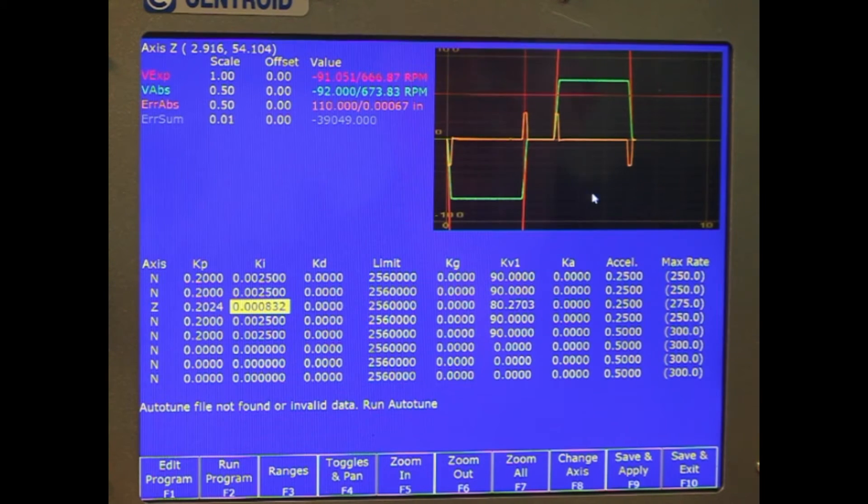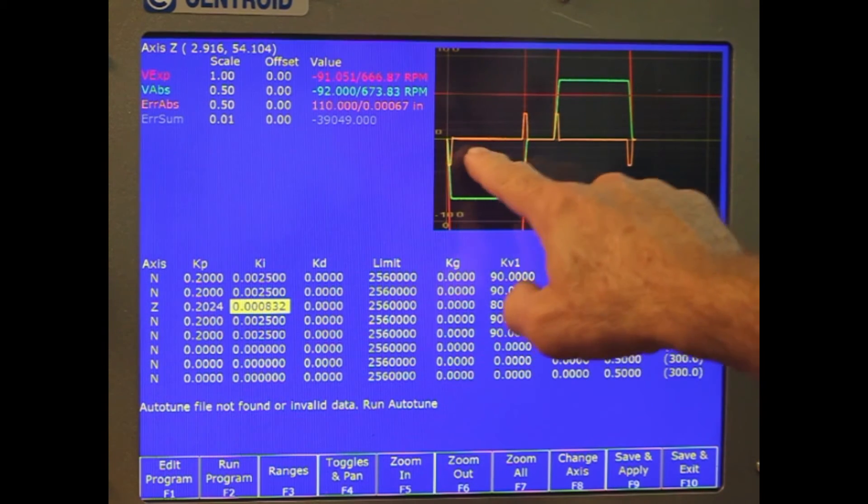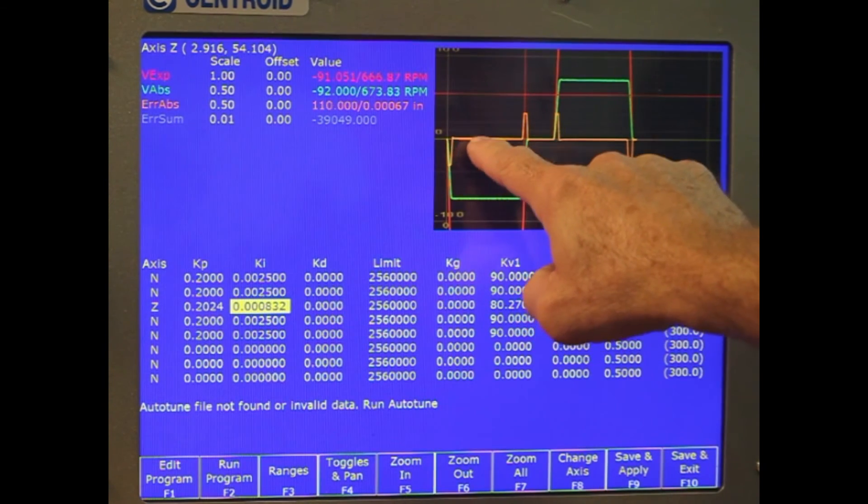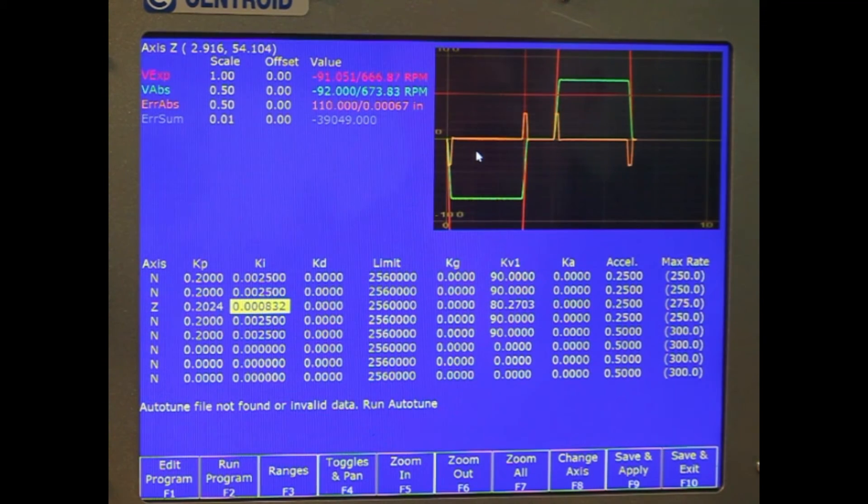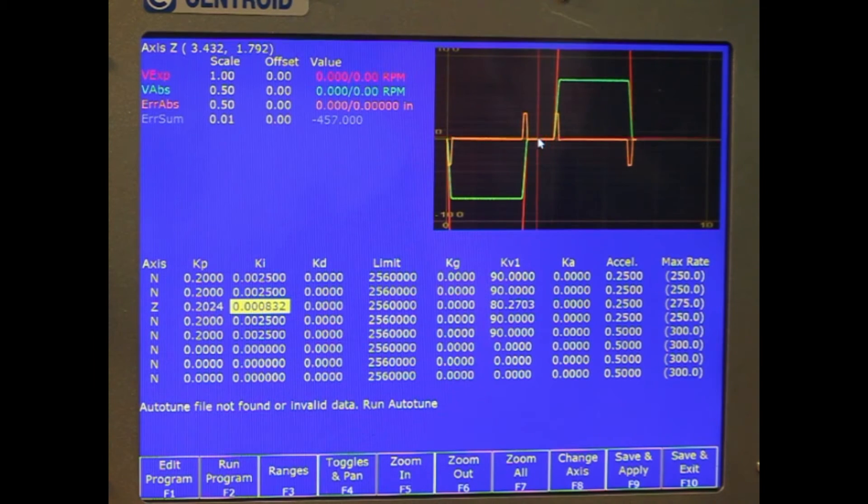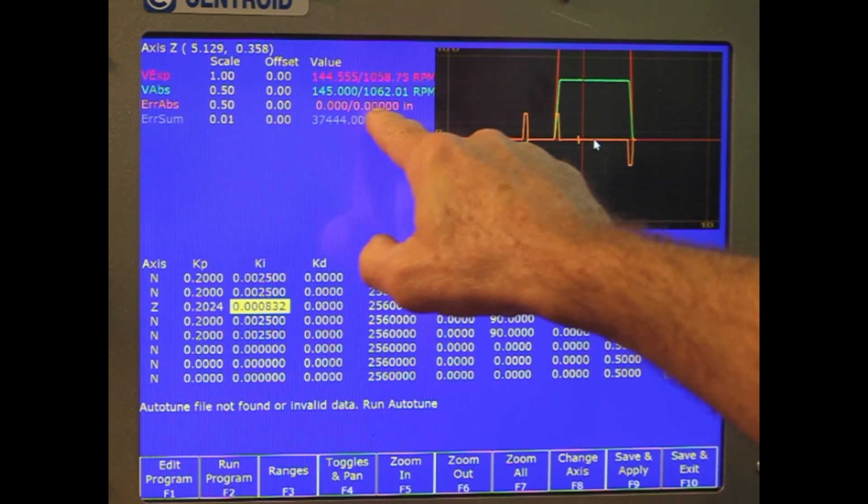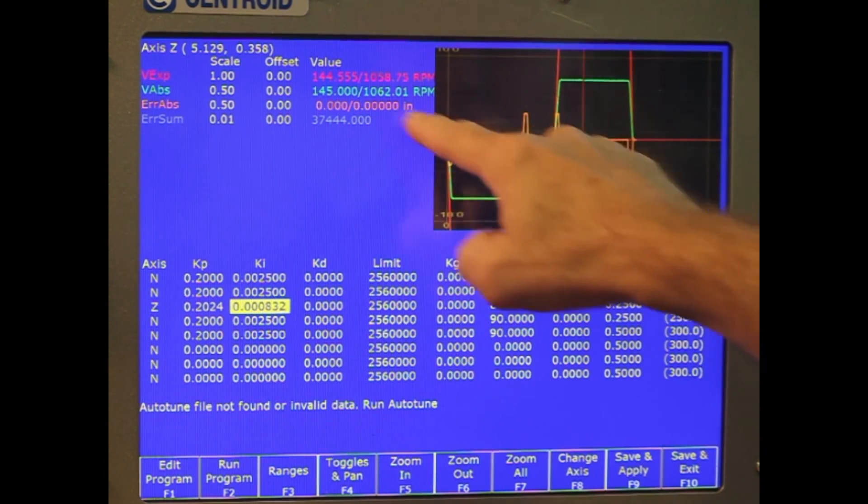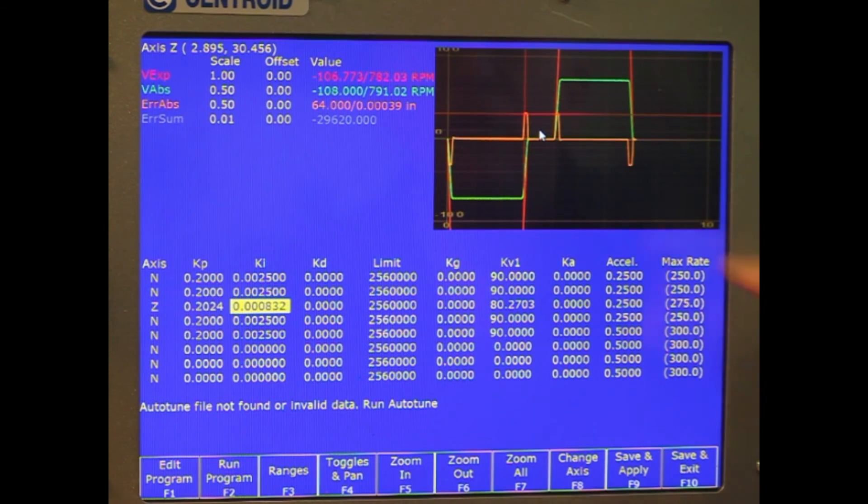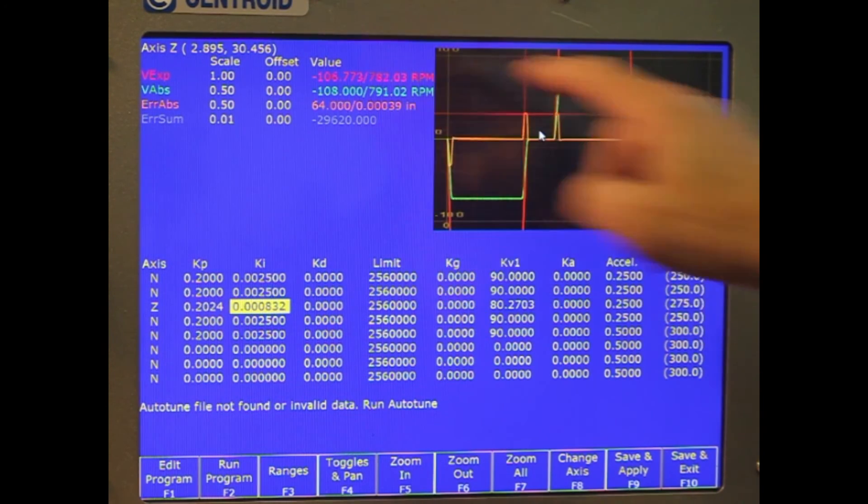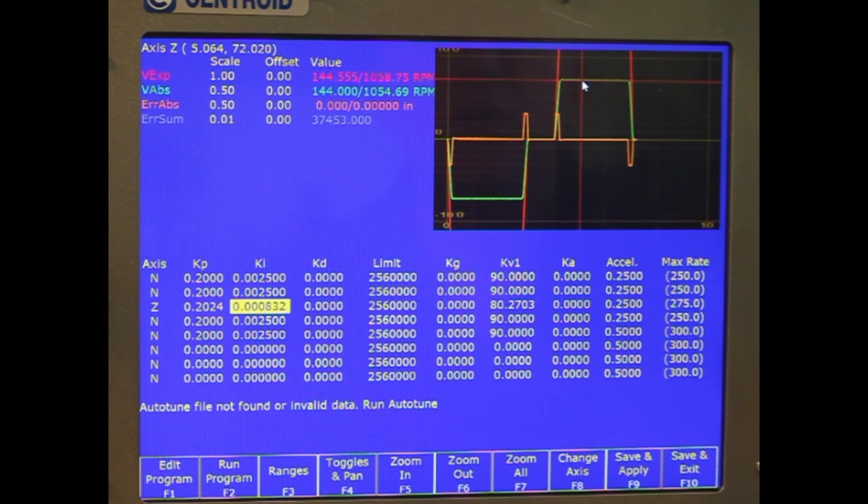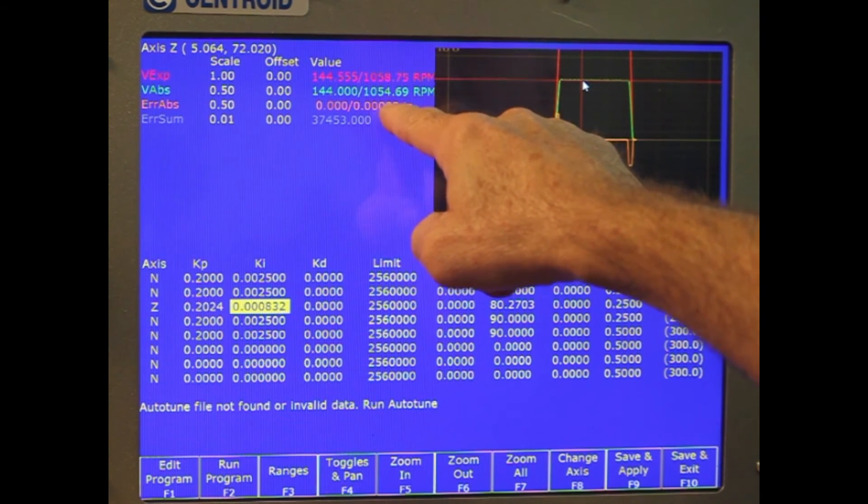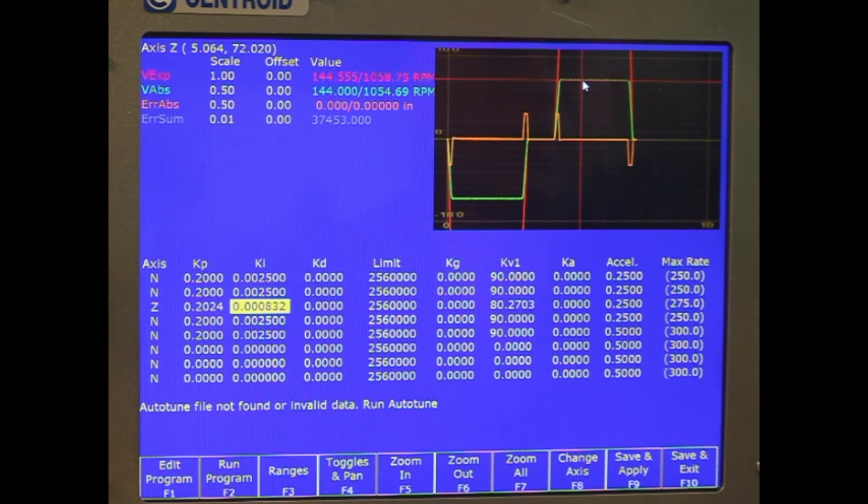And you can see right now, everything looks real good. If our KI was too big or KP was too big, you might see some oscillations in the middle here. And we can actually, with our mouse, move around to different spots and see what our error is at that point. So basically in steady state move, it's exactly where it needs to be. At the decel time, it's going out by four tenths. We can go to our green line here and look and see that our motor is actually at that point running 1,000 RPM.